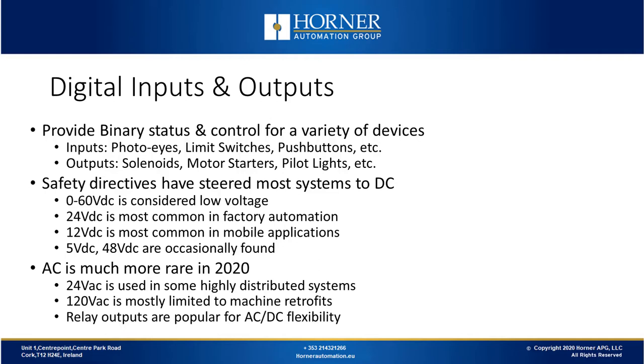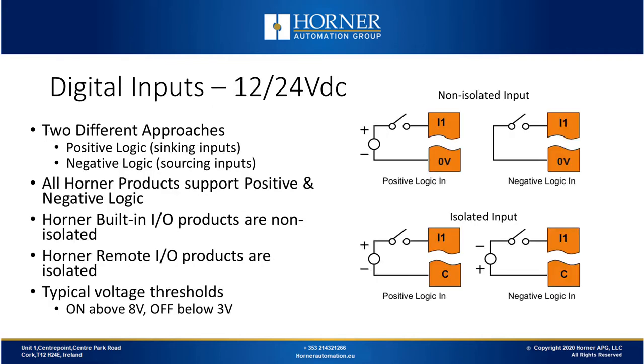From the standpoint of wiring digital inputs, there are two different approaches. You've got positive logic where you run the positive lead through the switch and into the input module. There are also some subtle differences in wiring depending on whether the inputs are isolated or non-isolated. The Horner built-in IO that's built into the OCS is typically non-isolated. For our remote IO products, they're almost always isolated, so the main difference is what you do with common. For isolated inputs, you're actually going to connect the plus lead from your power supply to the common. Typical voltage thresholds for our products are on above 8 volts and off below 3 volts.